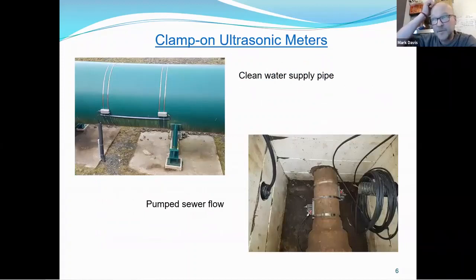So let's look at some examples of ultrasonic flow meters. These are clamp-on, so they do not interfere with the flow. You can install and remove them without shutting the flow down, and they're suitable for clean water, raw sewage, effluent, even flows with heavily laden silt, again with the correct type of meter. Top picture, a very nice clean water supply pipe. The lower picture shows quite an old corroded cast iron pipe. Again, it's not a problem, as long as the rust is removed where we put the probes. You can see we have a probe on the left side of the pipe and a probe on the right, which effectively look at each other at about a 45 degree angle to measure the flow.